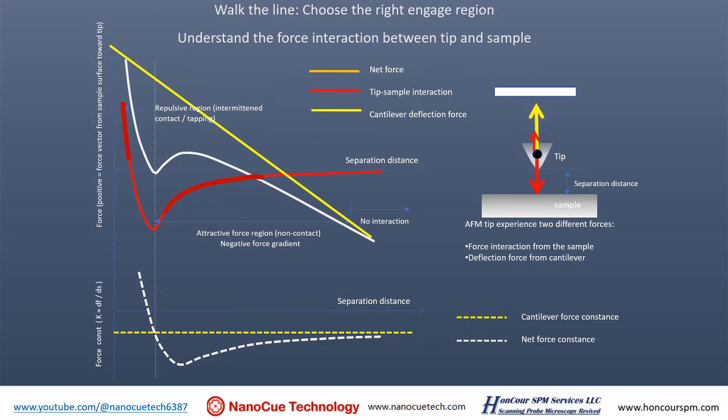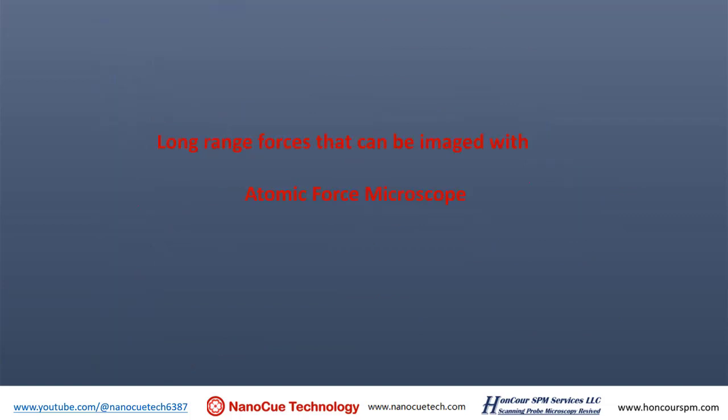This attractive and repulsive force causes a big shift of the cantilever's oscillation resonance. When the tip-sample interaction becomes repulsive, the energy of the vibration is also damped by the surface, causing a big reduction of the vibration. The surface does not allow the tip to vibrate anymore because it repulses the tip. Those are short range forces, and we use this to do tapping mode.